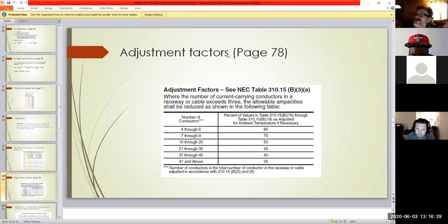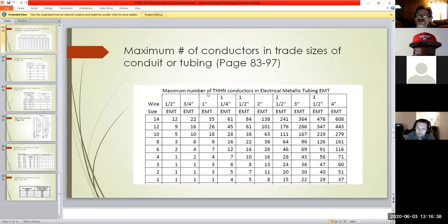The Uglies book - and this is all in the Uglies book, which is really awesome - you can literally carry it around, it's not a very big book, right at your fingertips. You can figure out, even to the point of running EMT, rigid conduit - how many wires can I fit inside a 3/4 inch EMT? If I'm running all number 14s, I could fit this many in there. That way I know my limit if I ever run into that situation.